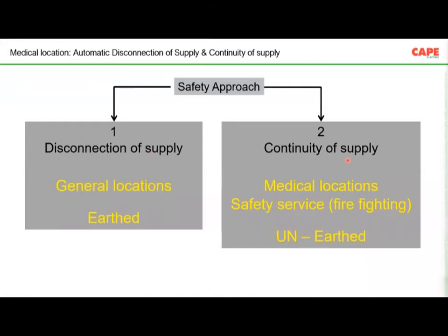What do we mean by continuity of supply? Continuity of supply means even if you use faulty equipment, or even if there is a first fault, the supply shall not disconnect. The supply shall continue. So also for fire services, for firefighting systems also, you can use the technique called continuity of supply, which is called an unearthed system. So basically, electrical systems are classified into earthed and unearthed systems. Earthed system means your MCB should trip immediately. Unearthed system means your MCB need not trip during the first fault.